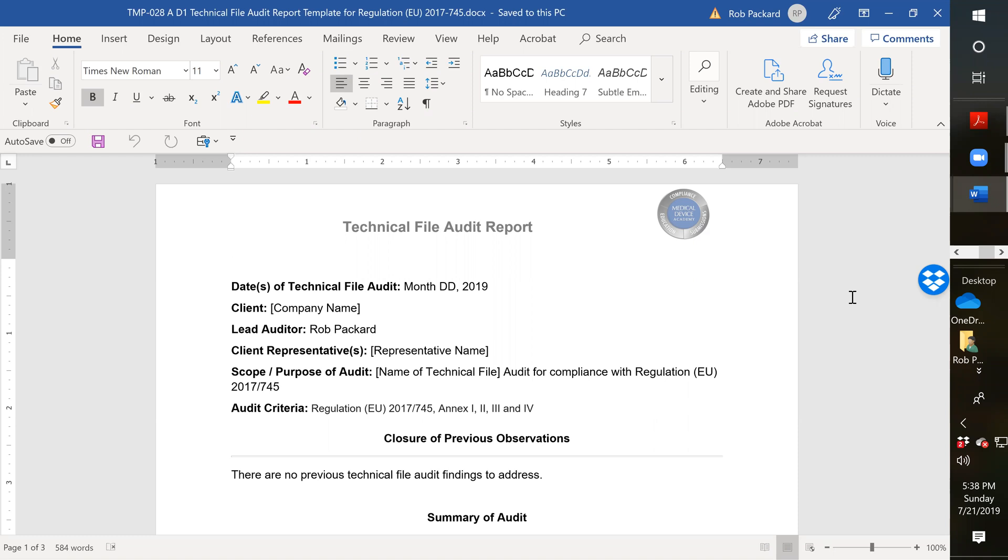One of the tasks that we're going to expect auditors to be looking for when they come to do a CE marking audit is to see if the company's actually conducted an internal audit of the technical files after they were updated. It's not enough just to update them, you also have to show that you're auditing your systems as well.